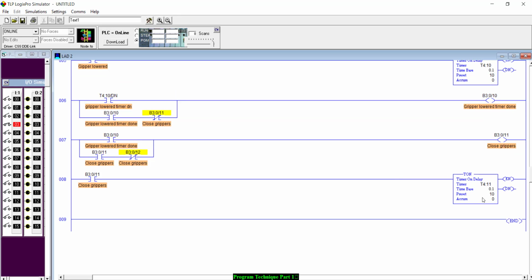One of the things that I used to do, when I was programming all the time, is I would set all my timers to the value of 5 seconds. Why? Because that way I knew it wasn't going to be a timer problem when I was troubleshooting. Everything was set to 5 seconds. So if something happened while I was programming with like a 5-second delay, I knew it had something to do with the timer. Like I had a bit that was in the wrong state or something going on with the timer in my logic caused me trouble. So that's a good rule of thumb there.